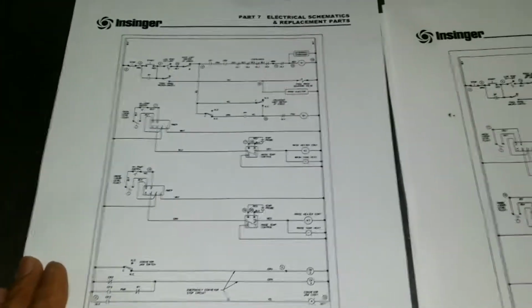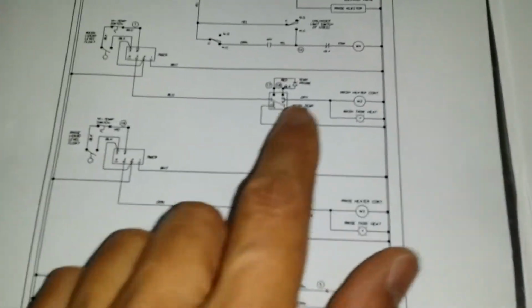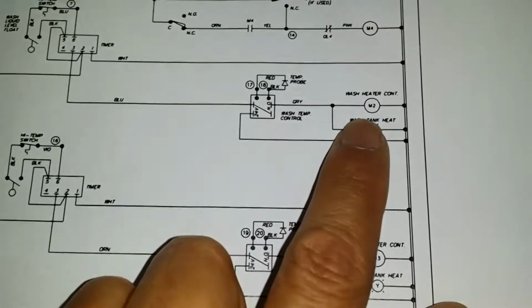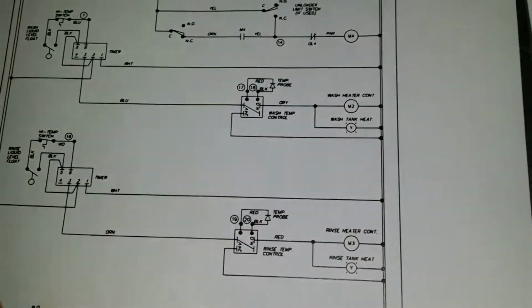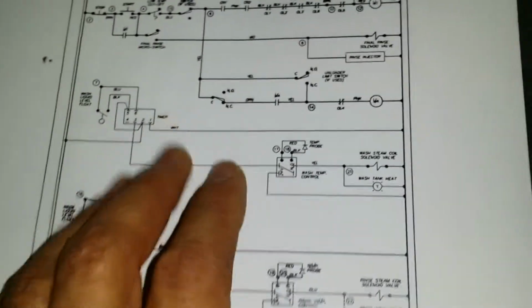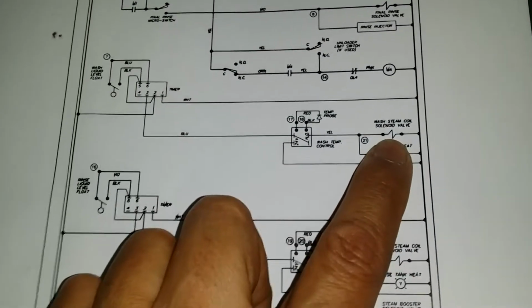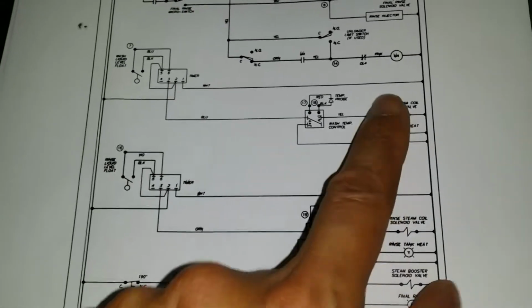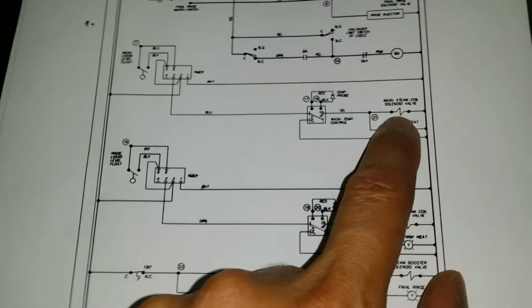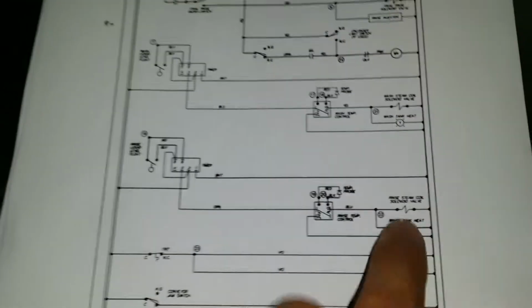Here I've got two schematics side by side. If you notice, this one energizes a contactor for the heater, so that's not the schematic I'm going to use. The one I'm going to use for my case is the one that controls solenoid valves, because ours opens and closes steam solenoids for heating.